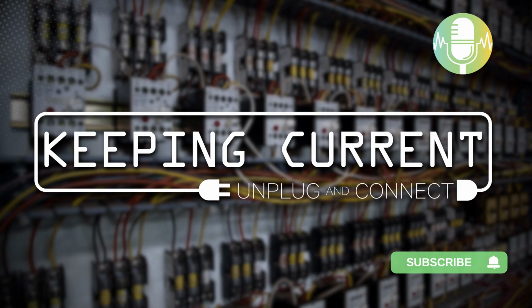One challenge and critical piece to consider is personal safety, because you can operate these systems remotely. You could be thousands of miles away and someone can log in and operate these systems. On the upside, this remote control lets site technicians minimize exposure, so they can be 100 or 300 feet away operating breakers and the inverter without standing in front of it. That's a definite positive for our technicians' safety.